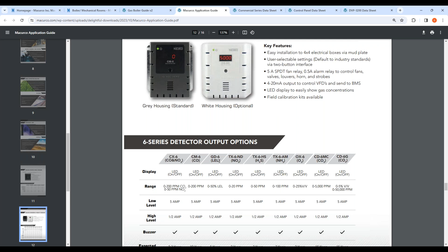Within each one of these detectors you have configurable adjustments. The key is the configuration menu is very simple, a 2-button interface, and the next gen product will be a simple interface too. You can take each one of these categories and adjust it how you want. The low level and high level relays stick at a 1/2 amp and 5 amp relay, those are concrete, dry contact Form C relays.